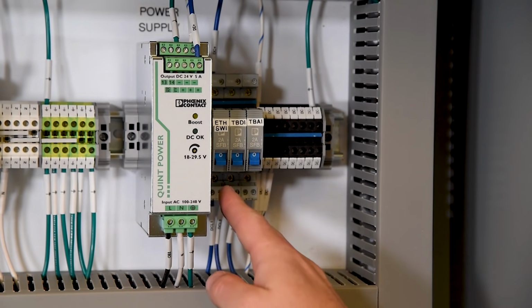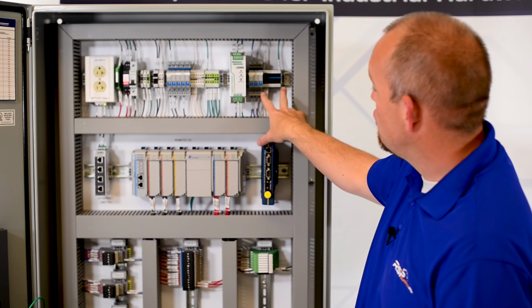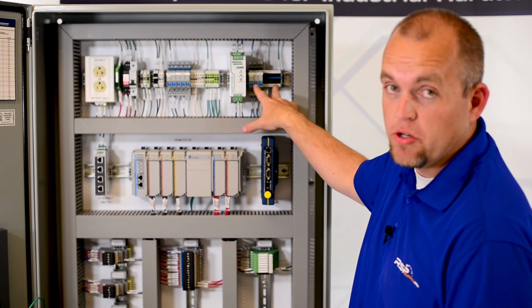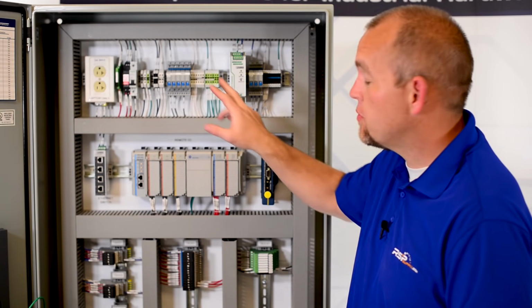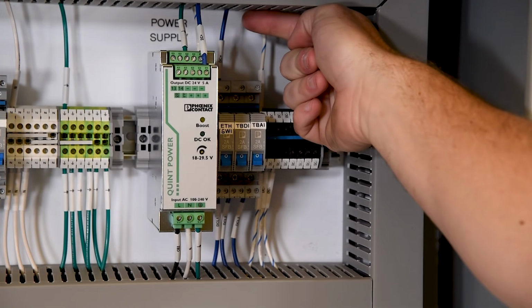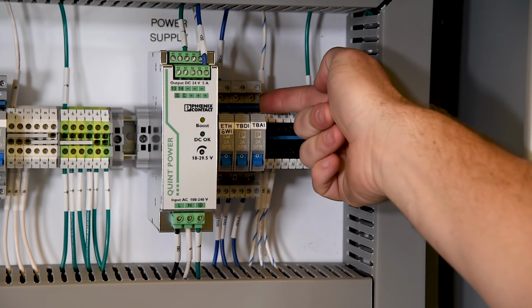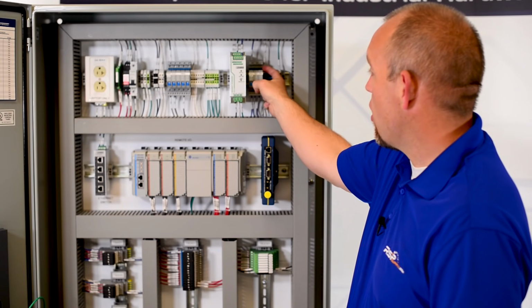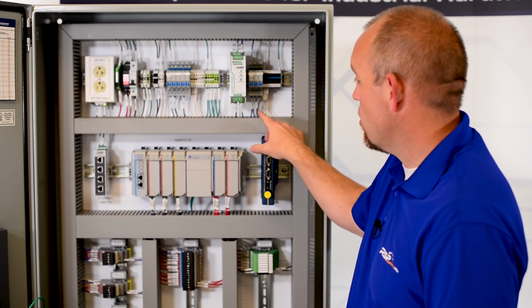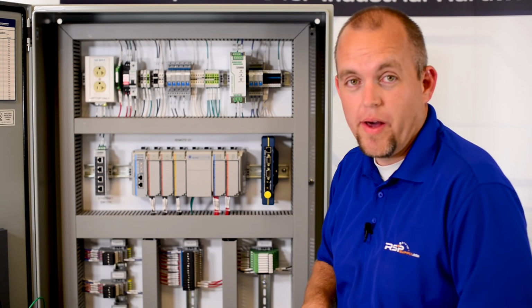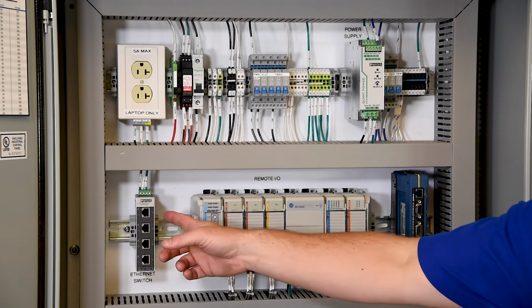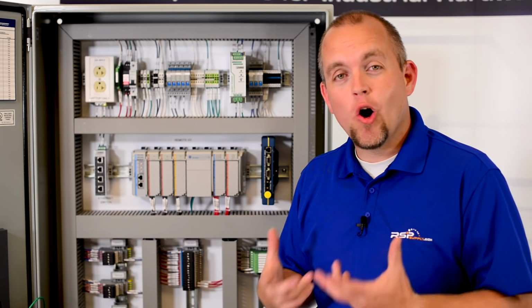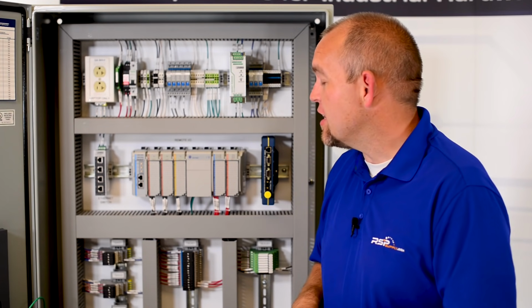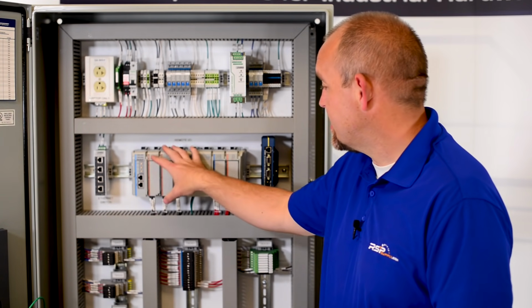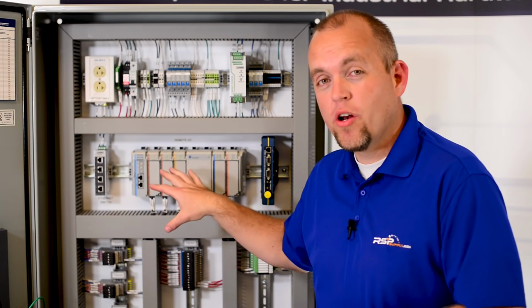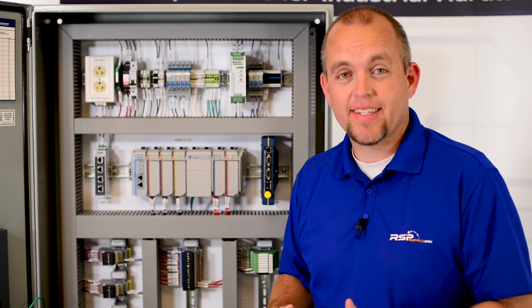From this power supply, we send our DC voltage to our DC power distribution. Just like with our AC power distribution, the DC power has one wire coming in, connects these three circuit breakers together with a jumper bar, and distributes that DC power to the components within our control panel. Moving on, we're now going to talk about the Ethernet switch. Much like you might see at home or in your place of business, the Ethernet switch simply allows the devices within the panel to communicate with one another using either a Cat5 or Cat6 cable.